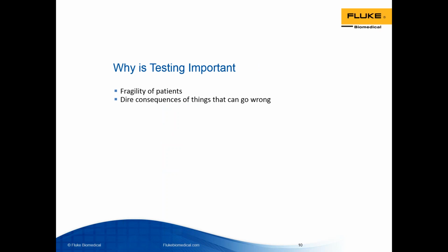So why is testing these incubators important? Well, clearly we've been mentioning how fragile these newborn, premature, and sick infants are, but I think that we say that so often it's become so generally true that we actually start to lose the meaning and the compassion behind that statement. So what happens when a parameter isn't in the acceptable range it should be? What happens when temperature is out of whack, even in just a corner of the mattress? What happens when humidity or sound is too high or too low?